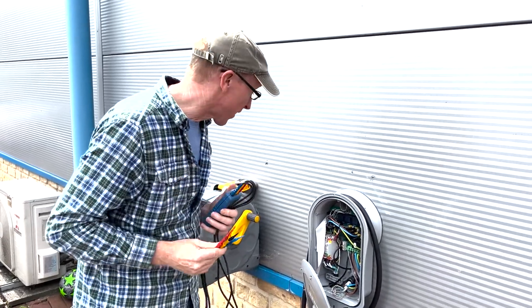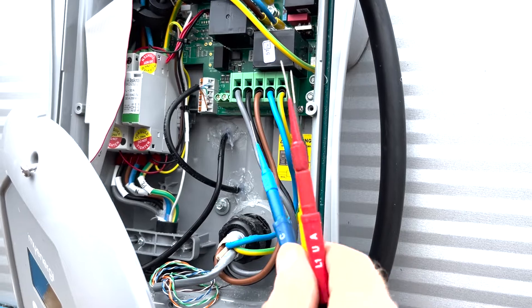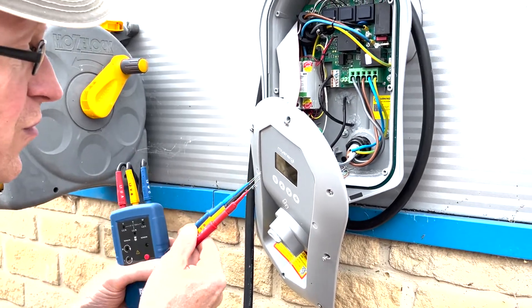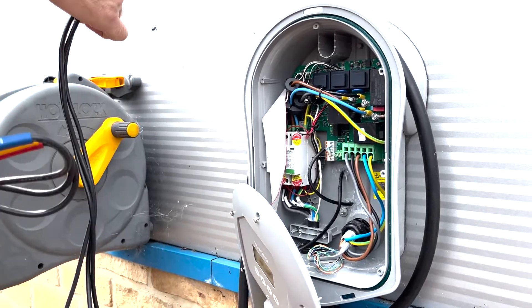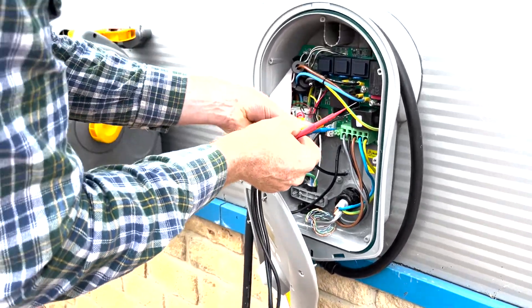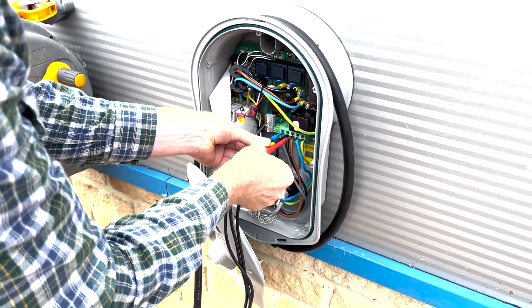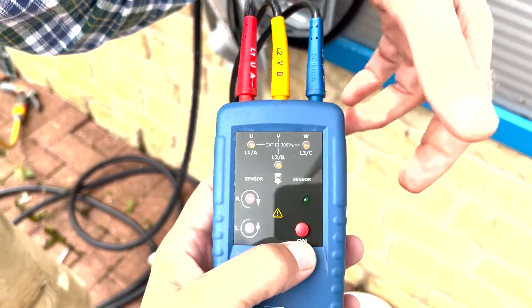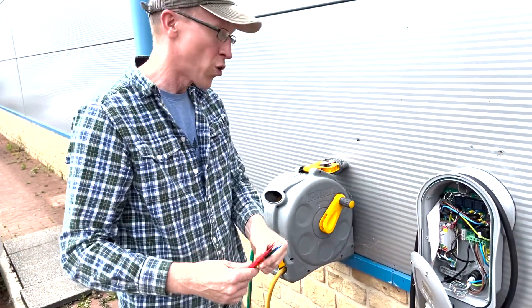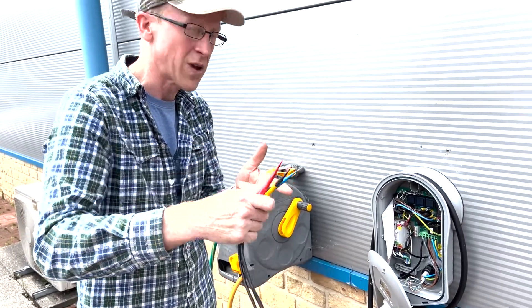We're now at the Zappi charger. If you look under here you've got earth, then neutral, then on the board it says one, two, three - the brown is one. I've got my leads with one, two, three in that order and this should give me clockwise. It's a bit dodgy but let me get those three in there. You've got three lights on - press the button - and it is rotating the same way, clockwise. So we now know the Zappi charger is good.